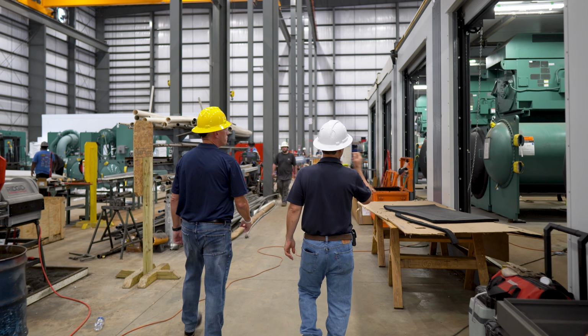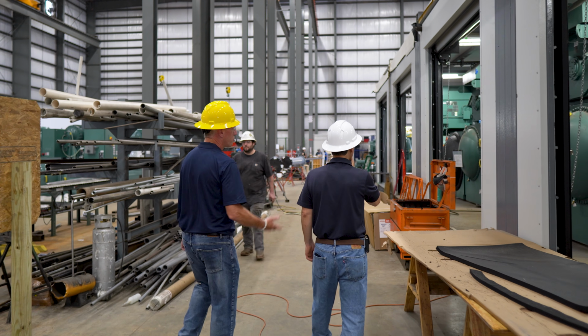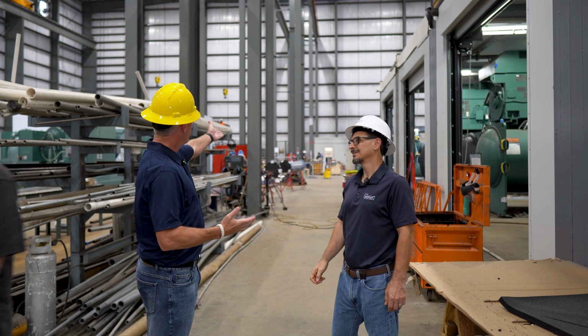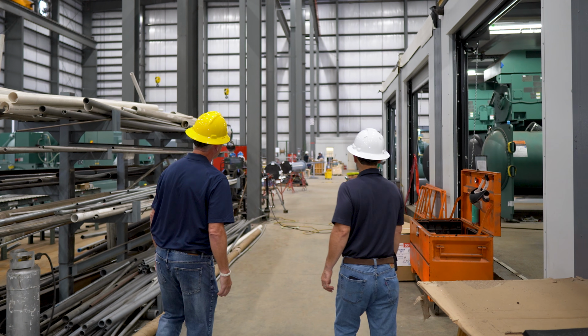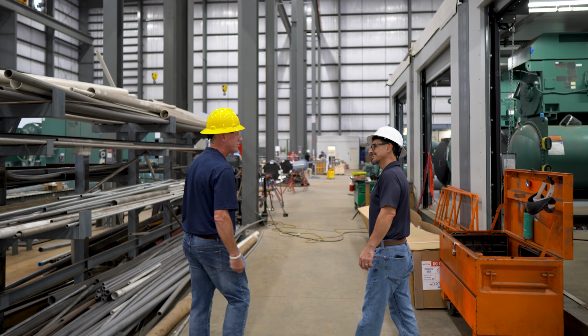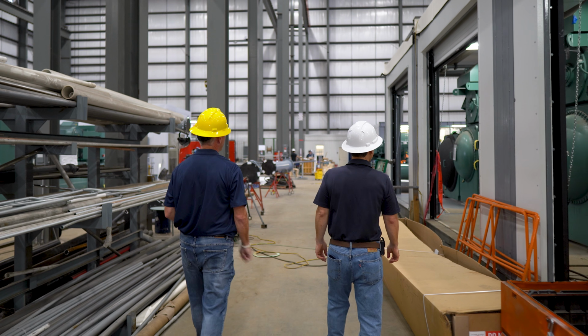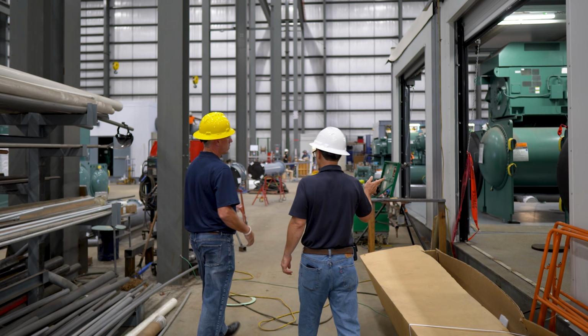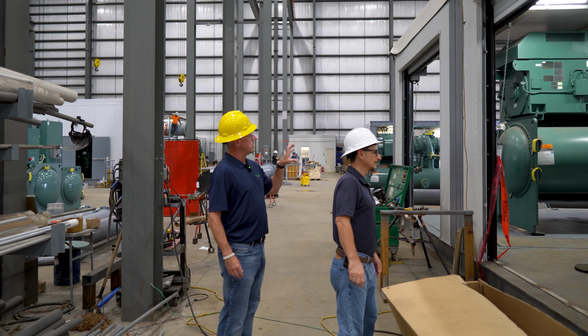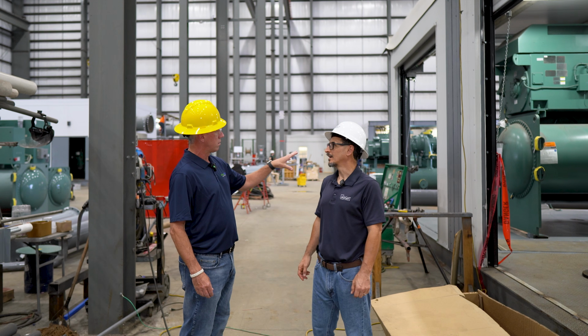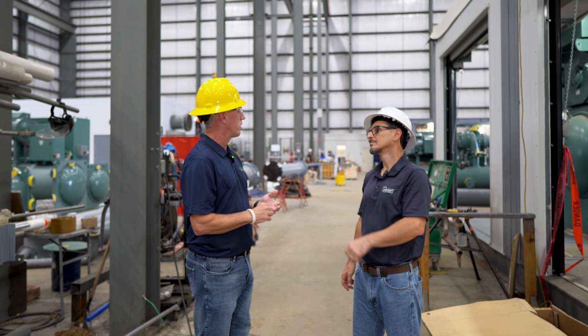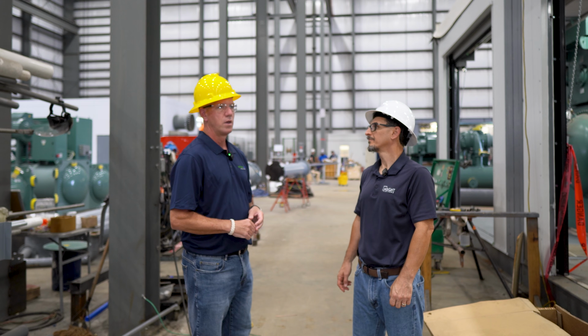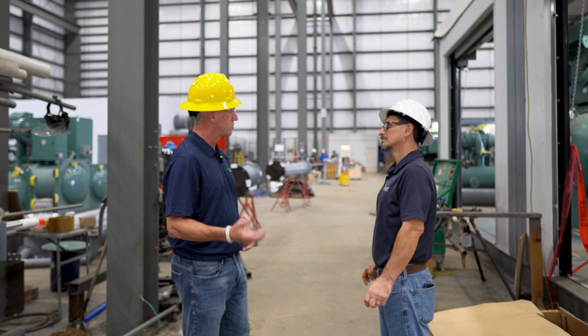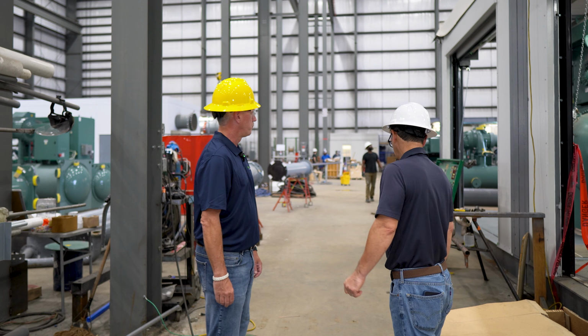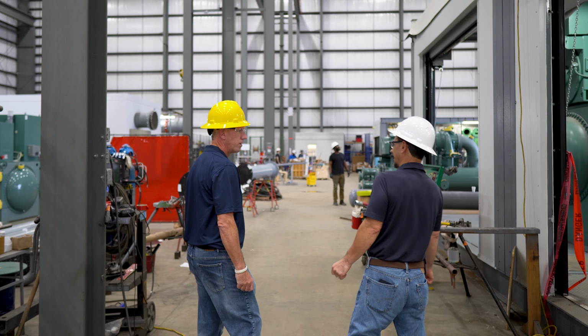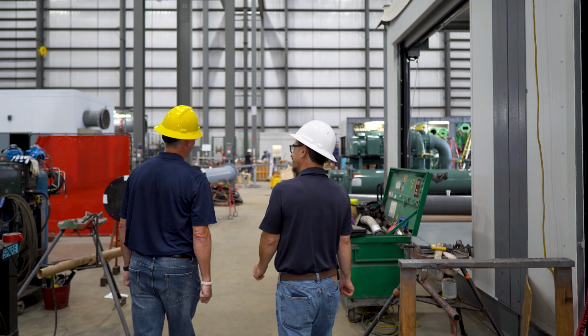We talked about the doors. It's kind of interesting, when you come down through here you see these big, huge machines, then you come up to another York chiller, probably a good size 300 or 400 ton machine, but it looks so small compared to a 1500 ton unit. Are you insulating these barrels here in the factory? JCI deploys it with the chilled water insulated, and the condenser water shell we don't insulate unless the client asks for it, depending on the climate, high humidity areas, and the dew point, and whether it's going to be inside the room. The first chiller plant I sold was in Jacksonville, Florida, and it was not conditioned. I learned about condenser insulation then.